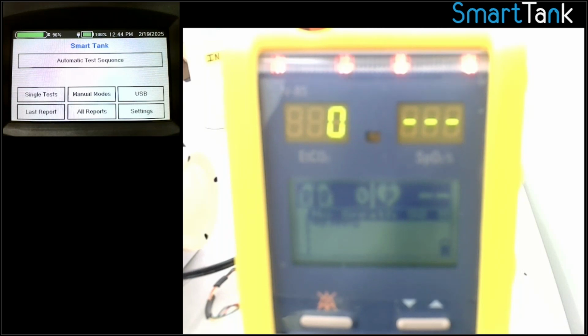They're usually a lot more complex. Some of those sequences will have 20 or 30 steps in them, 8 or 10 different tests, because you're doing full leak tests, you're doing flow rate tests, you're basically calibrating or checking each gas independently. And so the SmartTank will definitely facilitate all that. Great question.